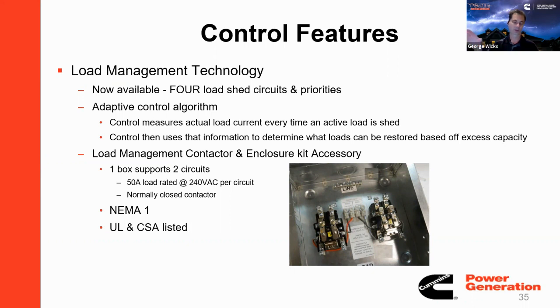And what we're going to do at startup of a power outage is have the generator control turn off large loads. What if it's a second air conditioner or a third air conditioner, a double oven, electric dryer, electric oven, anything that's deemed a large load. So we've got 4 of them, and they prioritize 1, 2, 3, 4. The system's going to turn them off and then signal each one to start 3 minutes later if certain conditions are met.